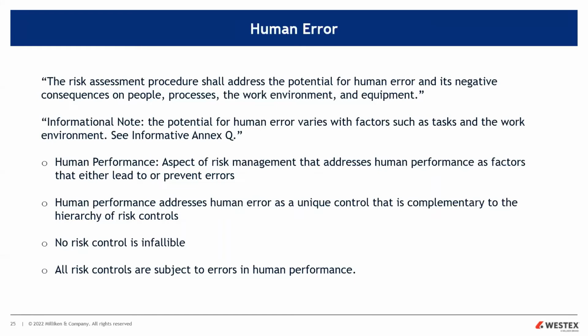I talked to a lot of people, a lot of safety people, and they're not aware of Annex Q, which is called human performance and electrical safety. And it's actually applicable to all the hazards, not just electrical hazards. But let's talk about human performance really quickly here. It's an aspect of risk management that addresses human performance that has factors that either lead to or prevent errors. Human performance addresses human error as a unique control that is complementary to the hierarchy of the risk controls. It's complementary to the pyramid.